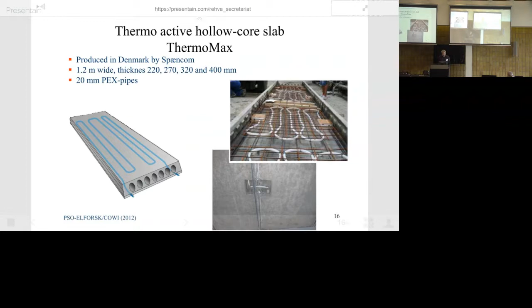But still, the main idea you see from this graph here, where you have the black one, is the load on the space during 24 hours. People come in, sunshine comes in, and normally when you have an air system, you use the peak load to dimension your system. So the idea with the other system was that during daytime, you don't circulate water, you don't remove anything from the concrete, you absorb, but you remove with your ventilation air. You need a certain amount of ventilation for air quality, and that's how much you can remove. So that's the maximum load you need for the cooling for the air system.